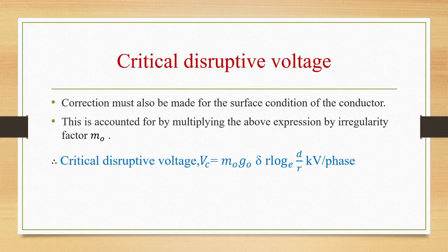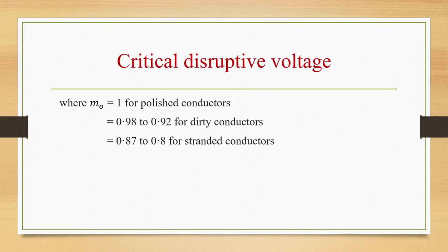Correction must also be made for the surface condition of the conductor, and this is accounted for by multiplying the above expression by the irregularity factor m naught. Therefore, critical disruptive voltage Vc can be given as m naught g naught delta r log d by r base e kilovolt per phase, where m naught is equal to 1 for polished conductors, m naught equal to 0.98 to 0.92 for dirty conductors, and m naught equal to 0.87 to 0.8 for stranded conductors.